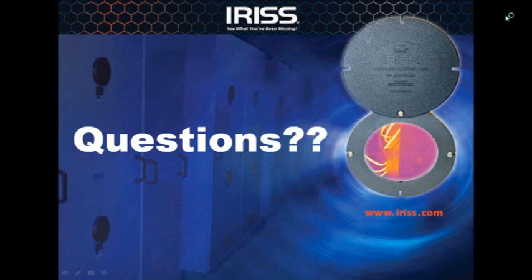Okay, great. Another one is, are ultrasound ports and IR ports one and the same? No. An infrared window is basically, years ago when we started using windows, we used to use grills. So you'd find IR windows that had a grill. And the good thing about having a grill was that you could do your infrared through it and you could do your ultrasound through it. But basically there was no barrier.